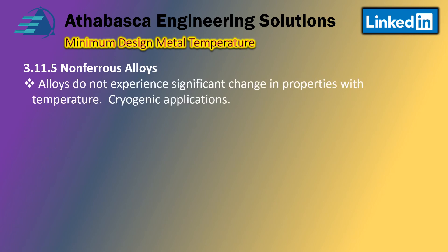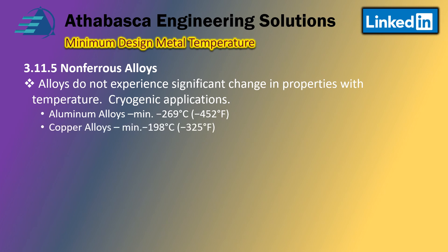Alloys that do not experience significant changes in properties are used for cryogenic applications. These materials don't have the same issues as carbon steel. For aluminum, you're good to minus 269°C — phenomenal, which is pretty close to absolute zero — which is why they're commonly used for refrigeration systems. For copper alloys you're down to minus 198°C. Titanium alloys are somewhat cryogenic, rated to minus 59°C or minus 75°F.